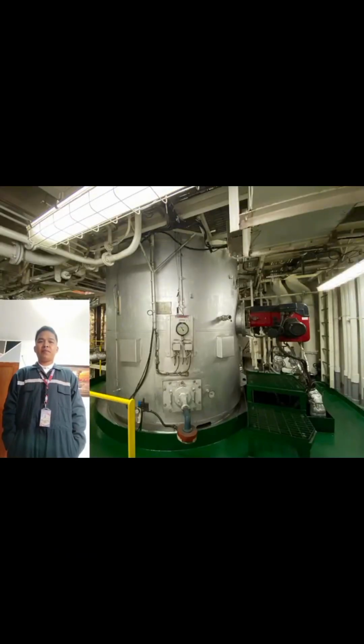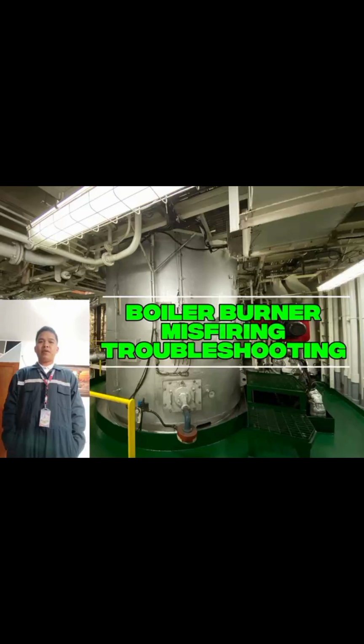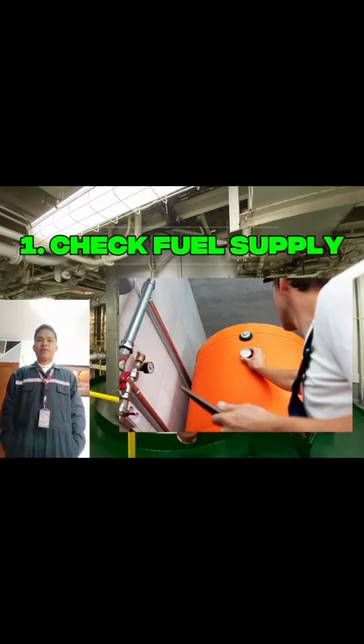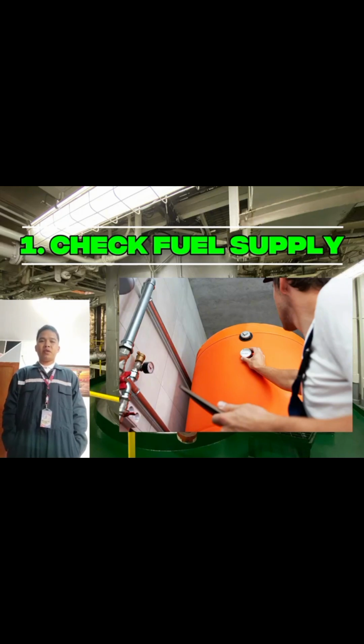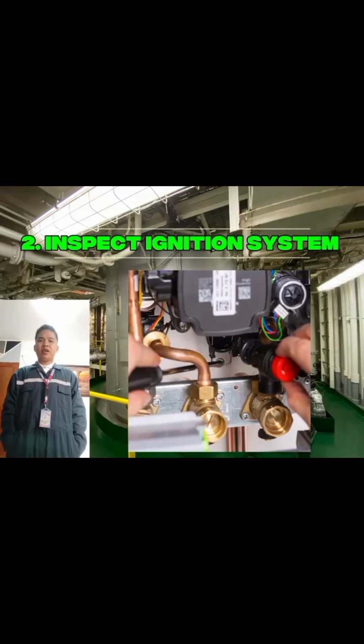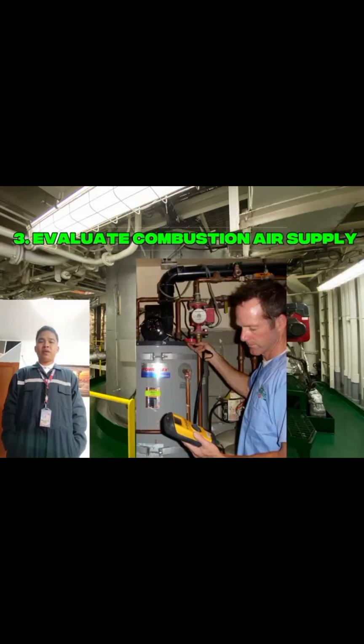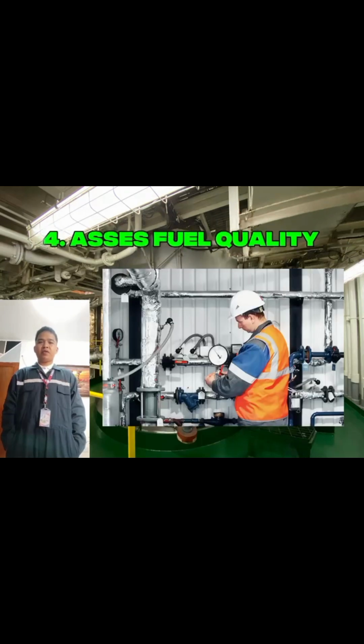The document outlines a four-step process for troubleshooting boiler burner misfiring. Check fuel supply: inspect fuel filters, verify fuel pressure and flow rate, and examine fuel pumps for any malfunctions. Inspect ignition system: check ignition electrodes, spark plug gap and alignment, and ignition cables and connectors for wear or damage. Evaluate combustion air supply: inspect the air intake, check air dampers and fans, and detect and seal any air leaks. Assess fuel quality: regularly monitor and test fuel for contaminants, ensuring it meets specified viscosity and flash point requirements.